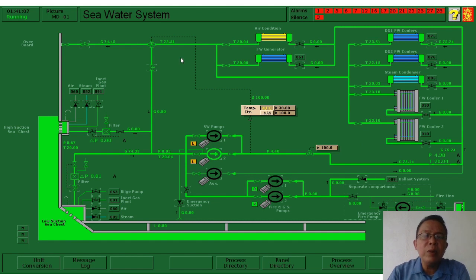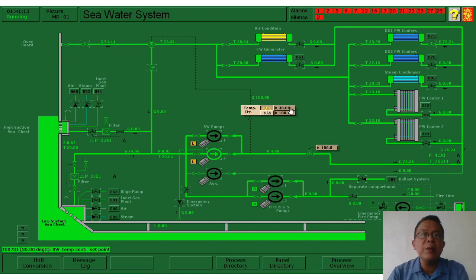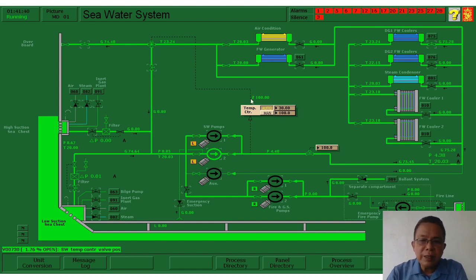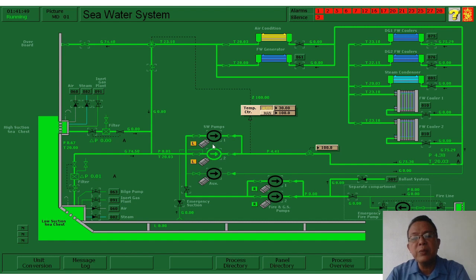So how do we maintain the temperature? By using our controller. We set the point here at 30 degrees centigrade — this is our set point. The controller manages the opening and closing of the three-way valve, closing the overboard and opening the bypass so the seawater bypasses overboard and is re-suctioned by the main pump. The controller monitors the feedback coming from the output, from the discharge of the main pump.